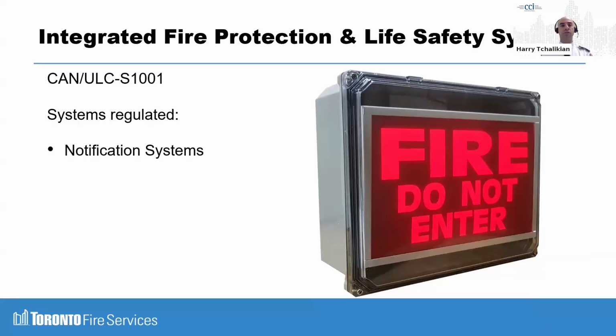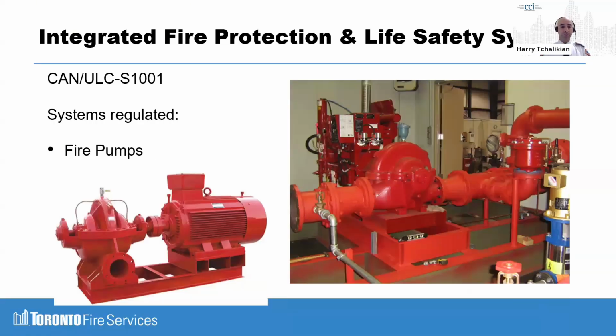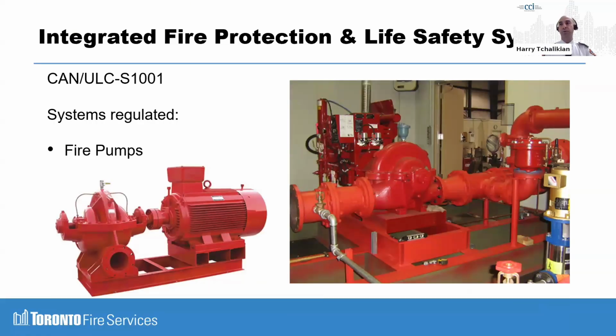Examples of things you're already doing: notification systems, like your fire alarm turning on fire, do not enter signs. Fire pumps, you're already doing this. You're already required under section 6.6 to test your fire pumps at full rated capacity. What the integrated CAN ULC S1001 requires is that you also simulate or actually test some of the failure features, like loss of phase and phase reversal, amongst other troubles that the fire pump can undergo that report to the fire alarm system. So just a higher level of fire pump testing.